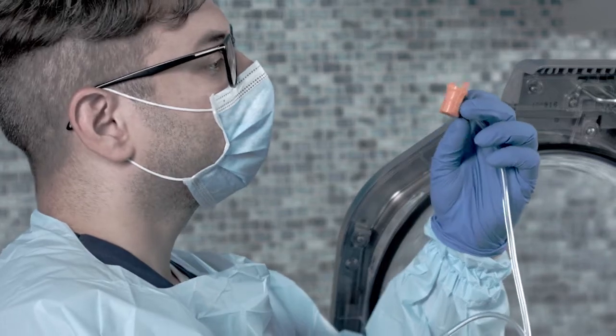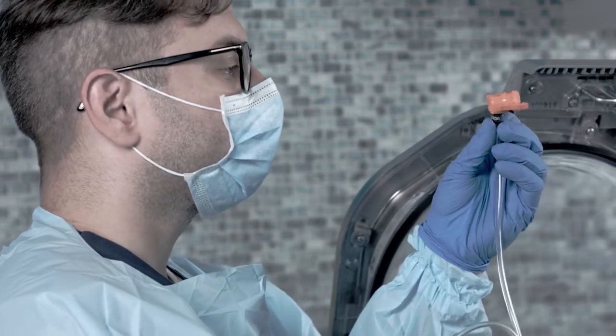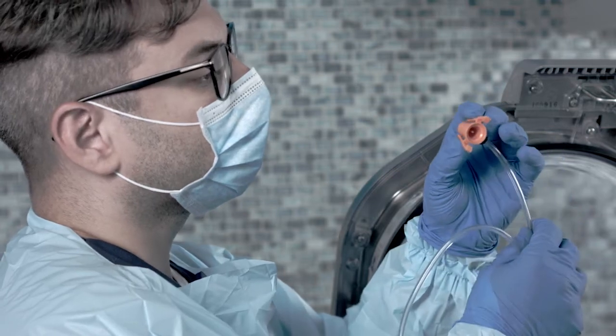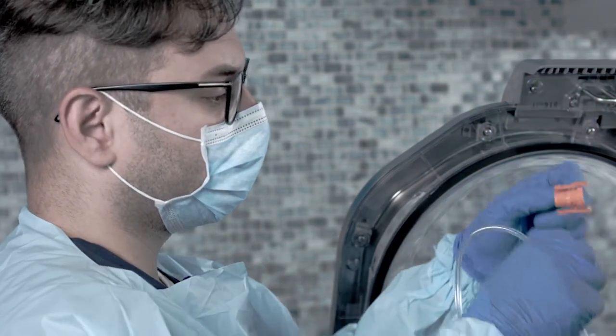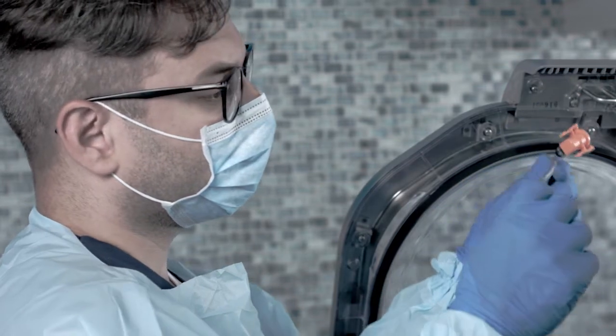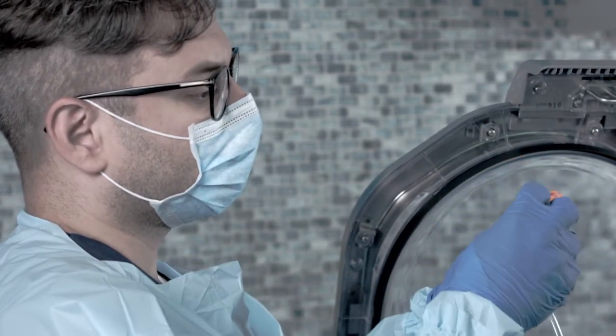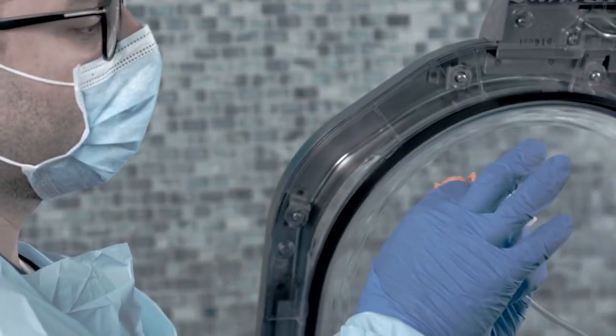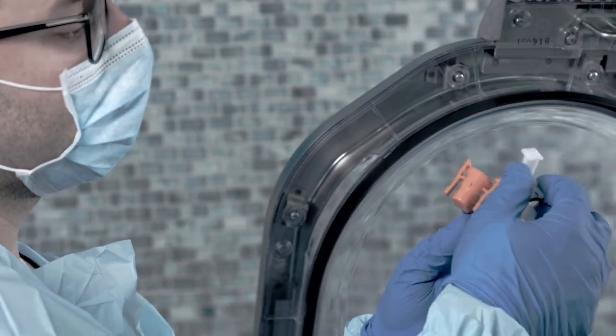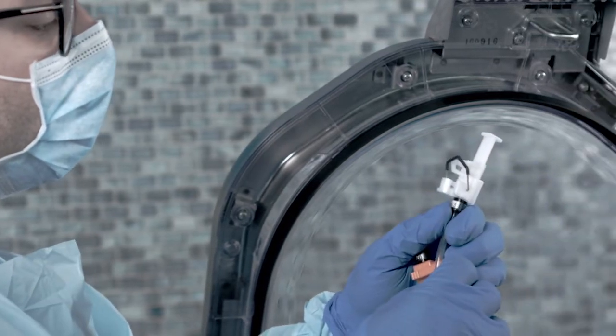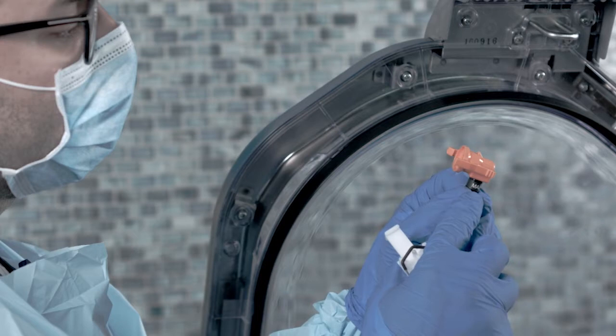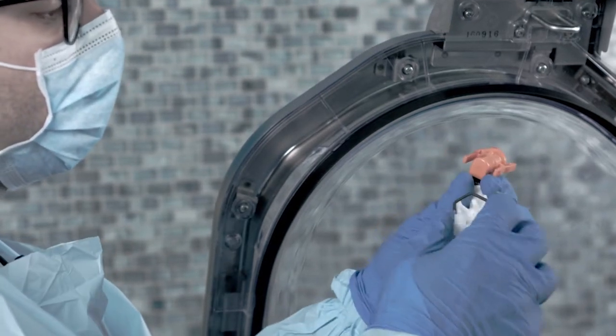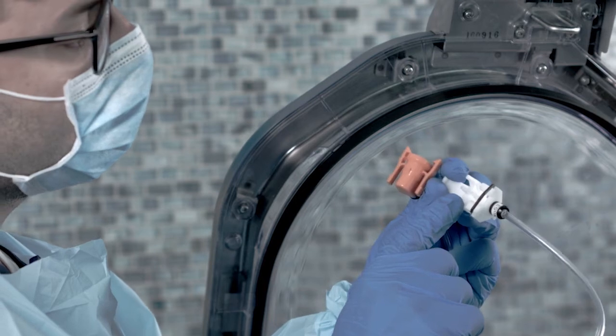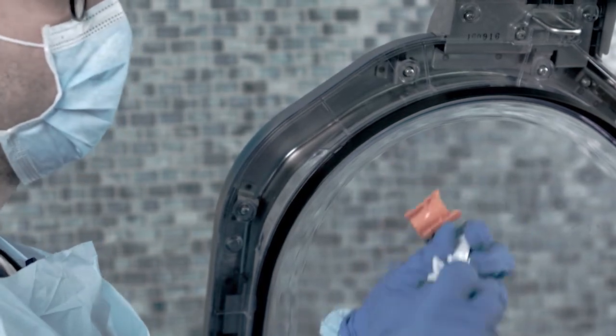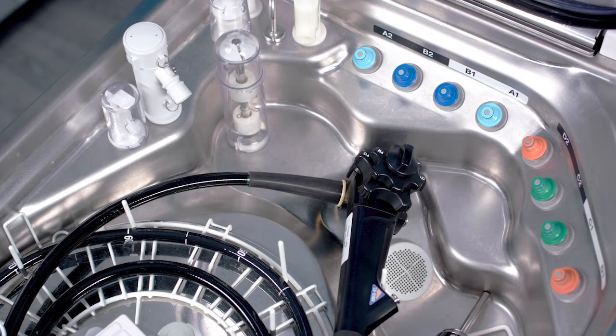Prior to connecting the MAJ2330 to the duodenoscope, we'll need to inspect it in order to ensure it is in good working order. Let's start by visually inspecting the connecting tube to ensure there are no cracks, breaks, debris, or irregularities. Now, move the lock lever of the connector to make sure that it functions properly and the lever is not broken. Then, visually inspect the pin on the connector. Make sure it's not cracked or broken. Finally, visually inspect the nozzle of the endoscope side connector to ensure that there are no bends or breaks. Now that we've inspected the MAJ2330, let's connect it to the duodenoscope.